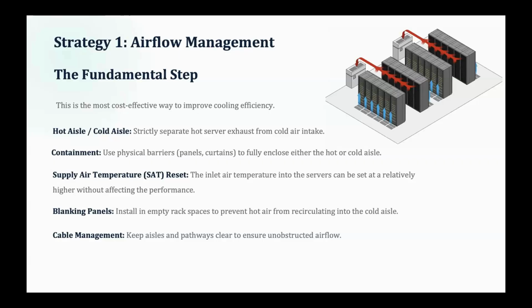Once you install a containment, the cold air cannot escape through gaps, and it has to pass through the servers only. In the server racks, if there are any gaps, those gaps need to be closed using blanking panels. So the conditioned air being supplied into the data center only has to pass through the servers to gain temperature and cool the servers, and then it is supplied back to the units to be reconditioned.